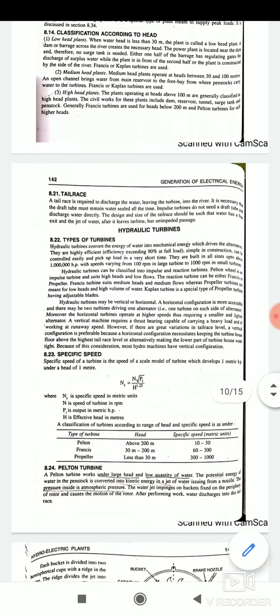Third one is high head plants. The plants operating at the heads above 100 meters, greater than 100 meters means the head height must be greater than 100 meters. Then that plant comes in the category of high head plants. The civil works for these plants include dam, reservoir, tunnel, surge tanks, and the penstocks. Generally Francis turbines are used for head below 200 meters and Pelton turbines used for higher than 200 meters. So this is all about the classification according to the head.